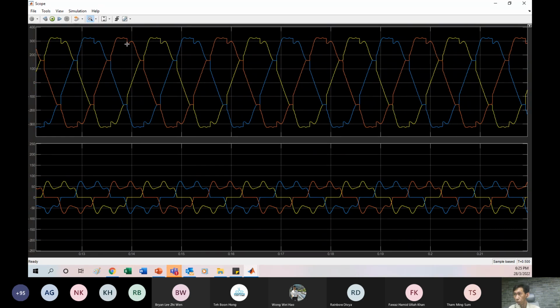This is what we call a voltage notch, and that means the harmonic is much more serious than with the inductor. Even with the inductor there are harmonics, but it helps smooth things a bit so that when you apply a filter, the filter power needed is lower and it's cheaper. If you don't do that, the filter to solve this problem becomes much more expensive.